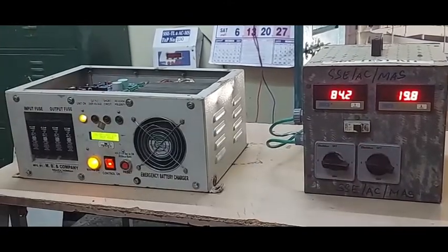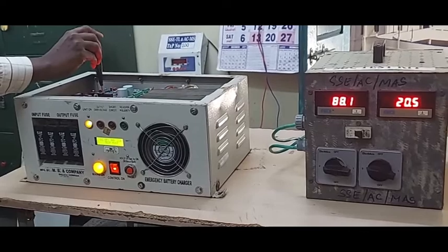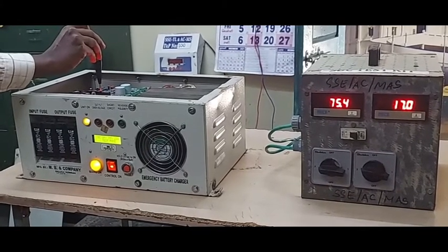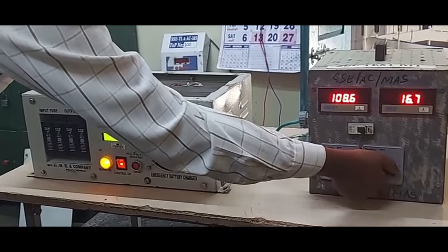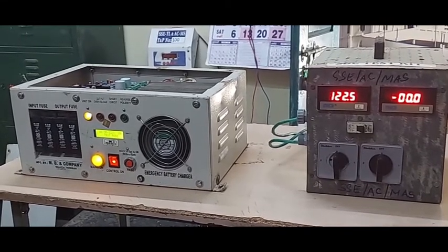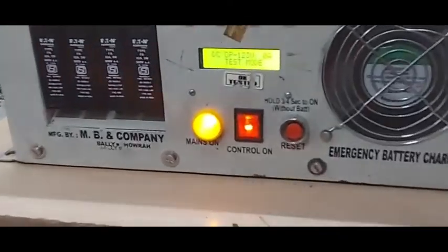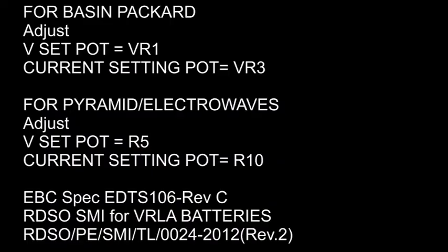Now, the current limit is set to 17 amps. Setting is verified. By this way, we can prevent premature failure of VRLA batteries, saving huge expense in purchase of new batteries. Thank you.